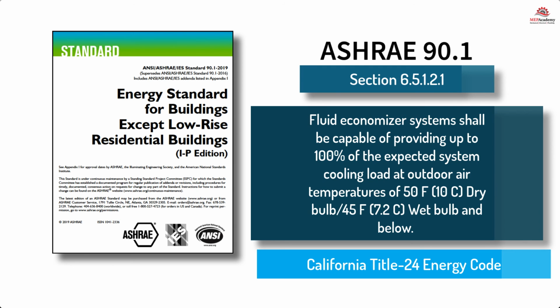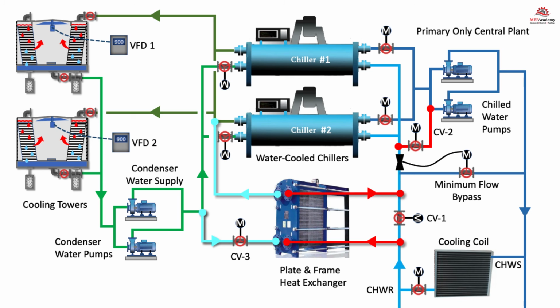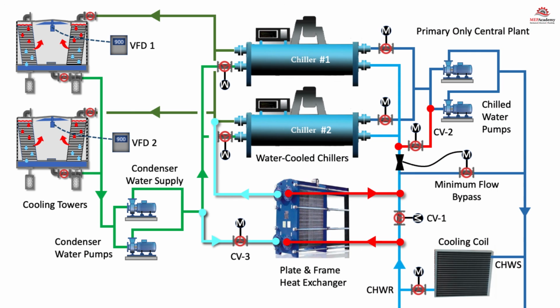When starting up the central plant, the control logic will determine whether to activate the economizer mode based on the two approach values being able to meet the chilled water supply temperature set point. Important temperatures. Some of the key temperatures to look for when determining if an economizer will work in your location is what they call the approach temperatures. This would take another video for an in-depth explanation, but we'll get you started with two approaches important for the integrated economizer systems we have explained in this video.